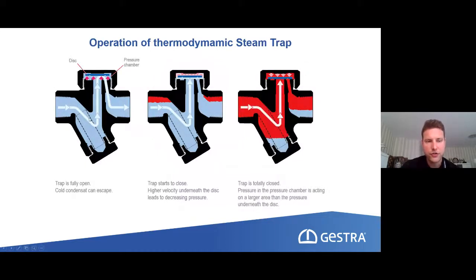We have here, let's say, the condensate traveling through the steam trap at a speed of half a meter per second up to 1 or 1.5 meters per second. This is slow enough so that the valve disc will be lifted up, and then the condensate can be discharged. If steam now comes to the steam trap, which should be blocked, this steam travels much faster through the system, on average, I would say, 25 meters per second. As soon as steam passes the valve disc, we have a pressure decrease, and the valve disc will be pulled onto the seat, and then it is shut tight. Then the steam bubble here first has to condense, so it has to become condensate again, and only then is it possible to open again when condensate comes to it.